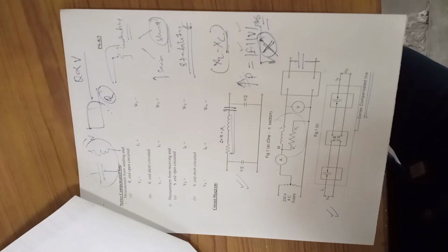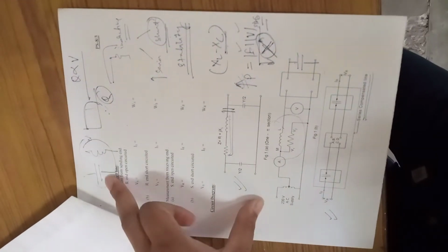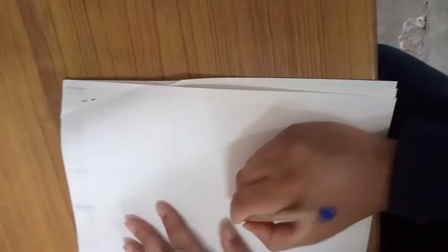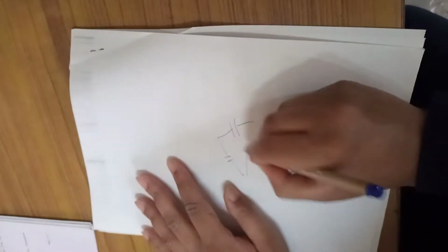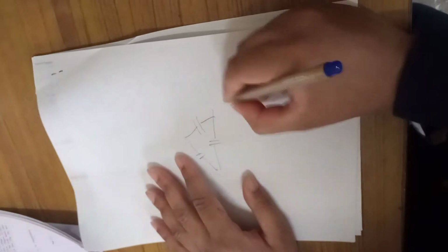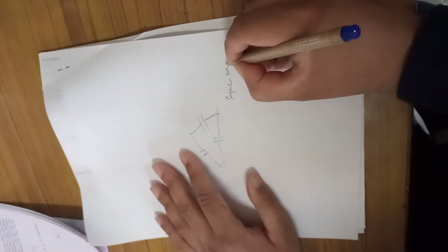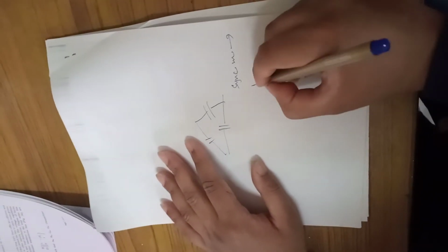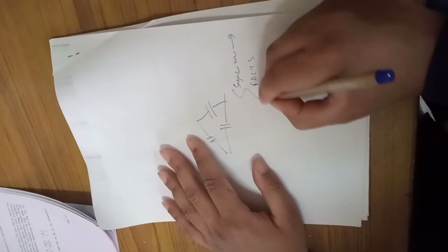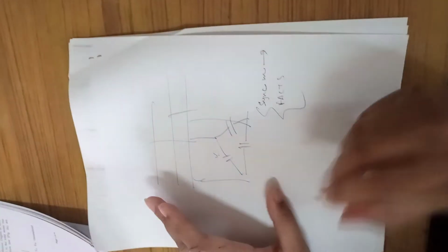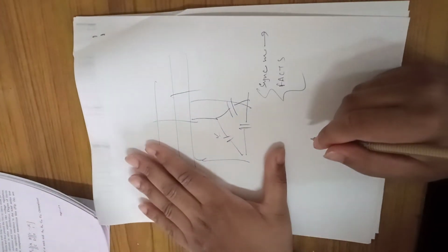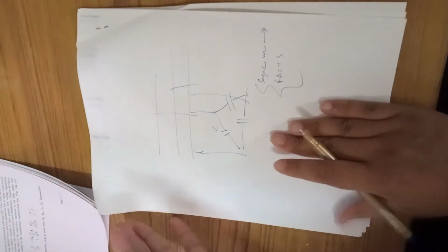So sometimes heavy reactive power is required in the transmission line. One of the techniques is to use capacitor banks. Okay, other techniques are also there. For example, you can use a synchronous motor in overexcited mode. They also supply reactive power. You can use FACTS devices, but the simplest solution is to use a capacitor bank which is directly connected to the three-phase transmission line. Okay, so this needs to be done. So this much is the theory.